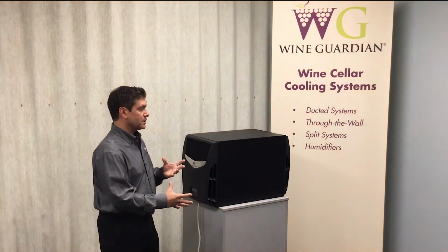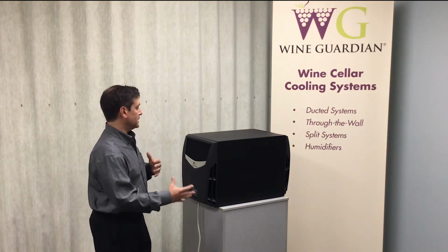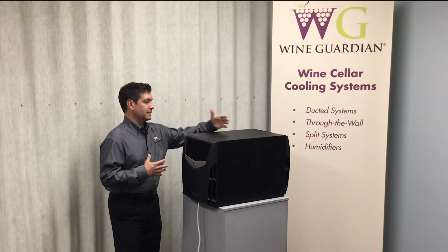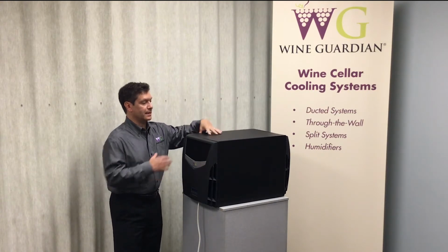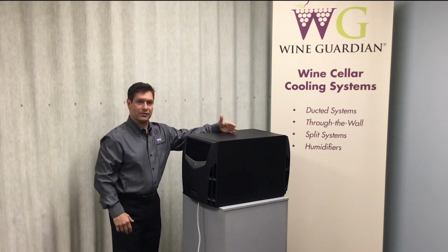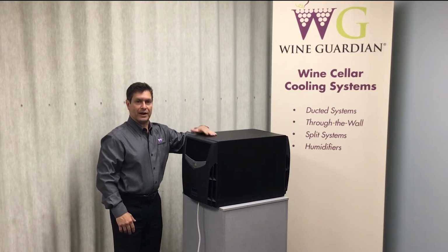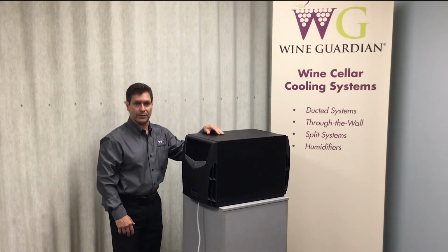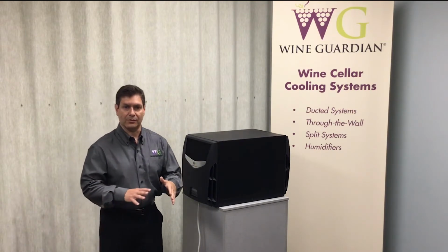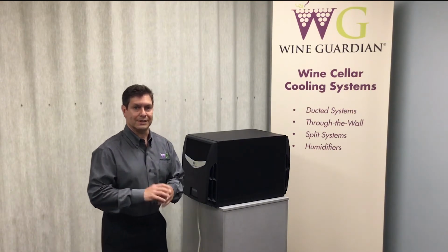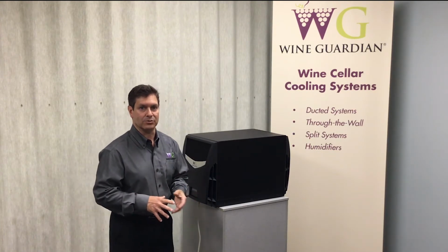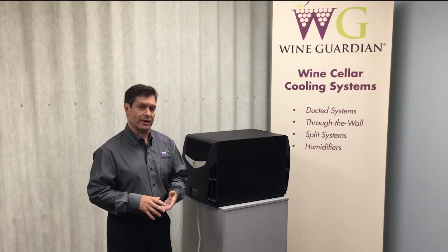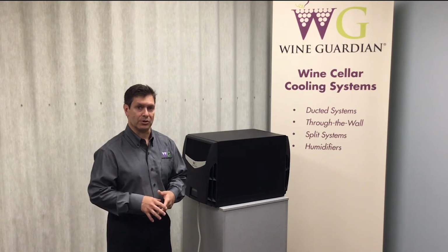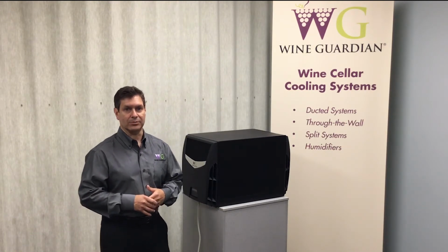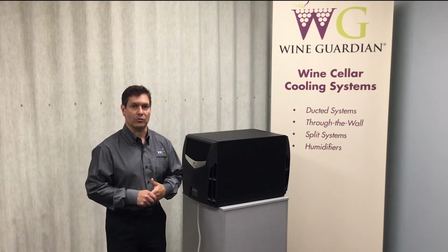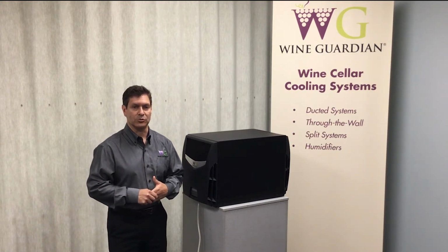So the way that this works, if you were to look at the system, is this is basically cut in half. If you were to take this top shell off, you would see a divider wall here, which divides the two sections of the unit. With our systems, we have two distinct sizes. We have a TTW 009, which is rated for about 1100 BTUs per hour. And we also have a TTW 018, which is rated for about 2100 BTUs per hour.